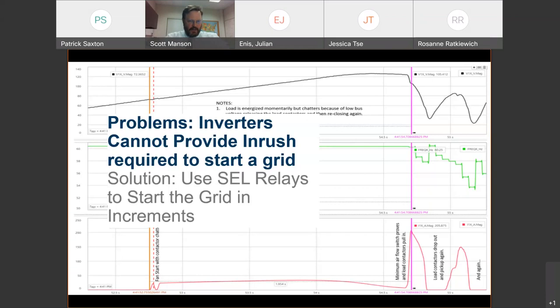To energize a power system, if you don't know this, you will now, you have to produce at least two times current to start a transformer. Transformers have magnetic phenomena that require a surge of current called inrush. Loads, either rotating kinetic loads, rotating motors, or power electronic loads, such as data centers, have a surge inrush as well. Power producing inverters on batteries and other systems that are sized for least cost to win bids do not produce enough current to energize your microgrid. Ouch. You can't start a power system with batteries. But you can with relays.